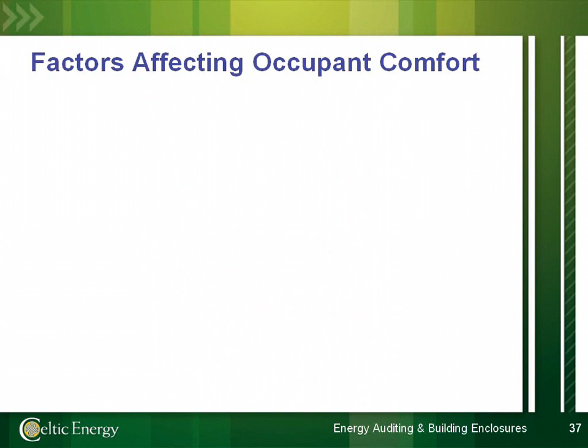Other things that affect building occupants include air temperature and movement. We've alluded to this, and with the client interview, some of these things can come to the forefront that will help guide us as we do our audit. We will look for the effects of air temperature and air movement because they have a big effect. A draft can cause occupants to be very uncomfortable. The relative humidity within a space can also be a big factor. If you're effectively controlling relative humidity in the summertime, occupants can tolerate a much higher dry bulb temperature within the space.